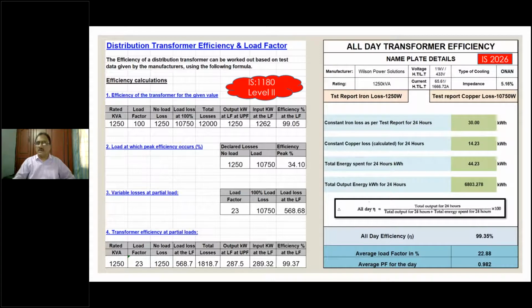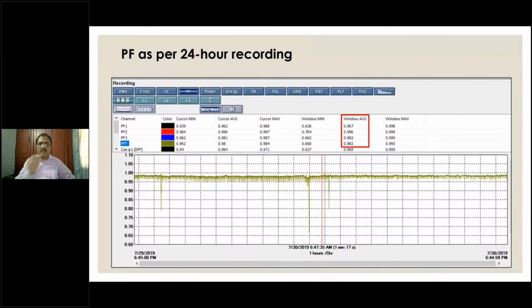Just one word of commentary. This transformer is as per IS 2026. This also was covered in the morning. If we now convert this transformer to IS 1180 level 2, then the value of energy saving will be even higher. The losses will be much lower. This 12 kilowatt loss would be approximately 9 kilowatts. So you will have 3 kilowatt unit saving per hour available to the industry, to the hospital.